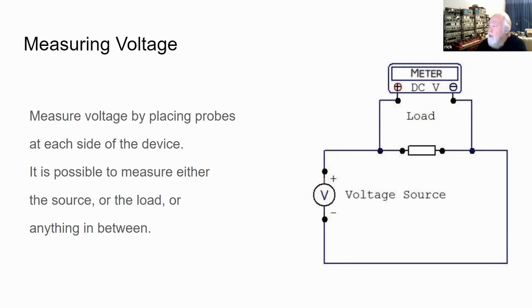If they are not equal, you could actually measure from the top of the battery where the plus is to the left side of the load and run the device with current through it. And you should not see more than a very, very small fraction of a volt, thousandths of a volt or even millionths of a volt, since the wire should be a good conductor. And if that reads okay, you can also try reading the negative side from the bottom of the battery over to the right-hand side of the load to see if the wire has any losses.